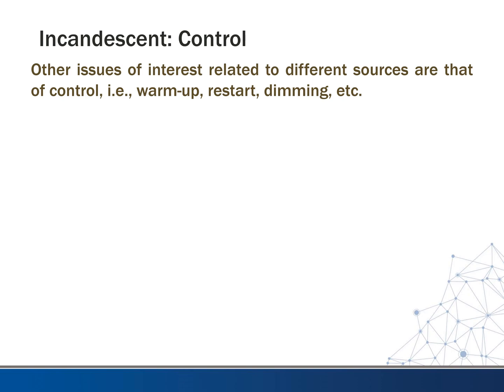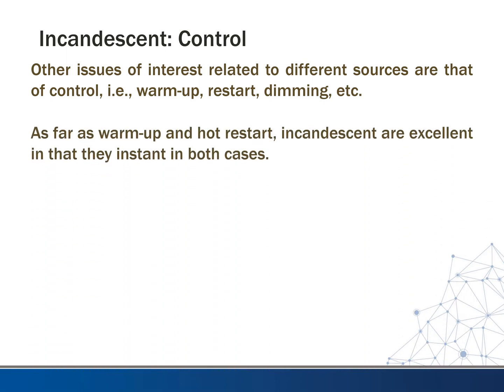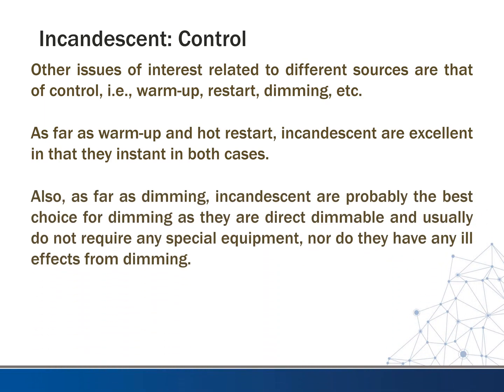Regarding control — other issues of interest related to different sources include warmup, restart, and dimming. As far as warmup and hot restart, incandescents are excellent in that they are instant in both cases; you can turn them off and on instantly. Also, as far as dimming, incandescents are probably the best choice, as they are directly dimmable and usually do not require any special equipment, nor do they have any ill effects from dimming such as possible hum, which you can get from other types of fixtures.